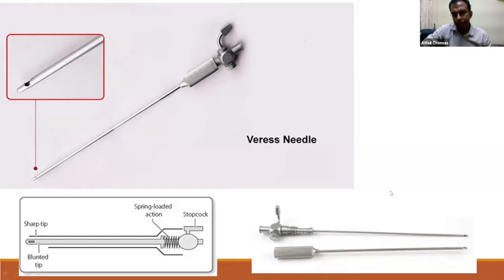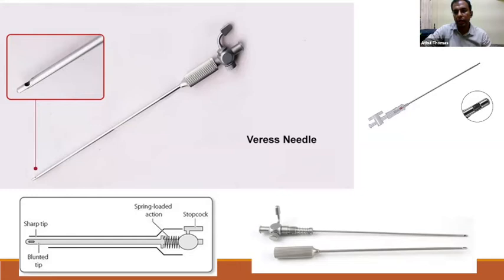When the assembly with the stylet in situ goes into a firm structure like the abdominal wall, the sharp outer cannula pierces the abdominal structures. Once it enters the peritoneal cavity, the inner blunt stylet pops out into the free space. This avoids bowel injury, which is the most important reason why we use the Veress needle.